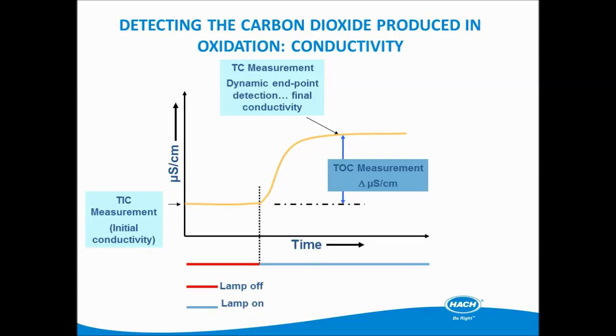Conductivity-based detection methods work by sensing an increase in ion concentration, which is attributed to the increased presence of bicarbonate and carbonate ions created from the oxidation of organic compounds. In this graph, conductivity of the unoxidized water sample is measured. The UV lamp then comes on to oxidize organics into carbon dioxide, which causes the conductivity to increase. Conductivity of the oxidized water sample is then measured to produce the TOC measurement value.